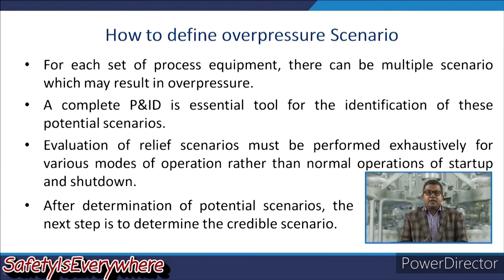Now, evaluation of relief scenarios must be performed exhaustively for various modes of operation, rather than only normal operation, including startup and shutdown. So, proper knowledge of the P&ID diagram is extremely important while you are evaluating the relief scenario. After determining the potential scenarios, the next step is to determine the credible scenario. A scenario that involves a single failure is called a credible scenario.